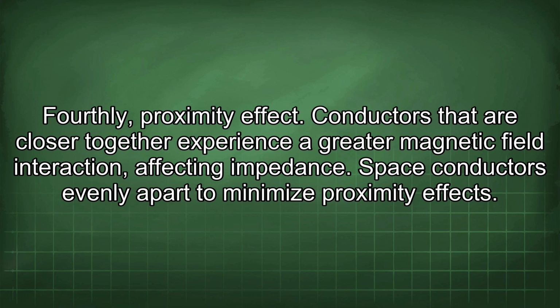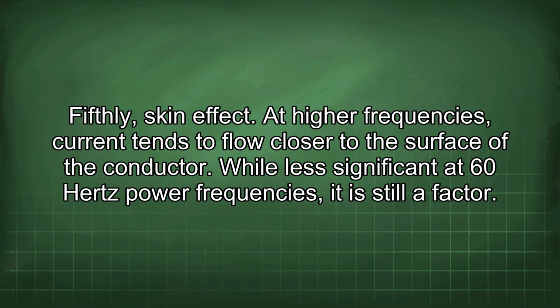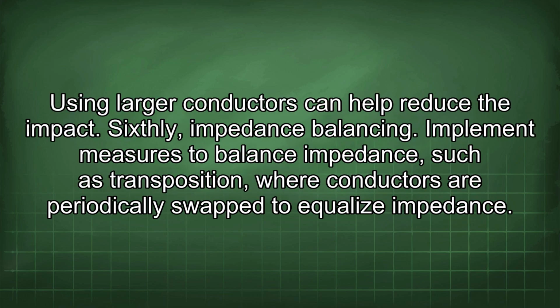Fourthly, proximity effect. Conductors that are closer together experience a greater magnetic field interaction affecting impedance. Space conductors evenly apart to minimize proximity effects. Fifthly, skin effect. At higher frequencies, current tends to flow closer to the surface of the conductor. While less significant at 60 Hz power frequencies, it is still a factor. Using larger conductors can help reduce the impact. Sixthly, impedance balancing. Implement measures to balance impedance, such as transposition, where conductors are periodically swapped to equalize impedance.